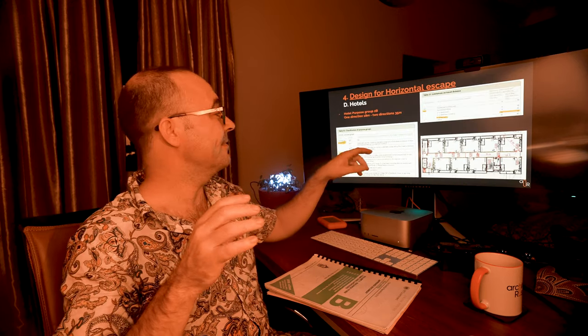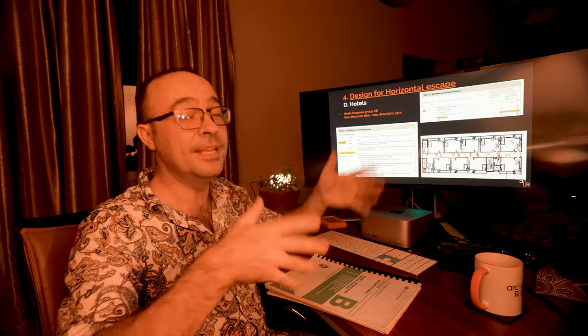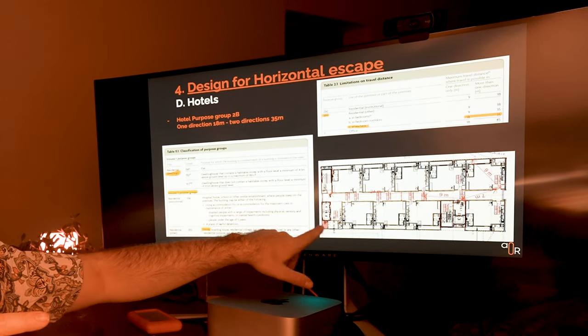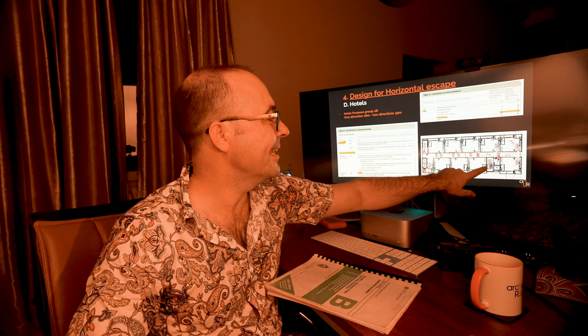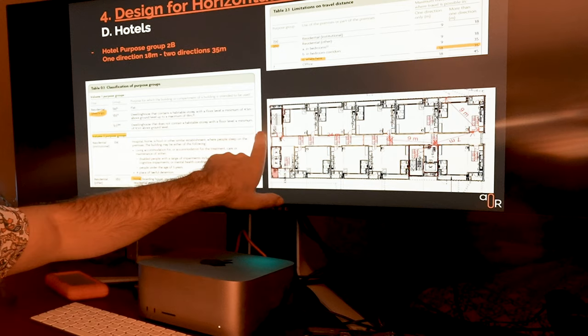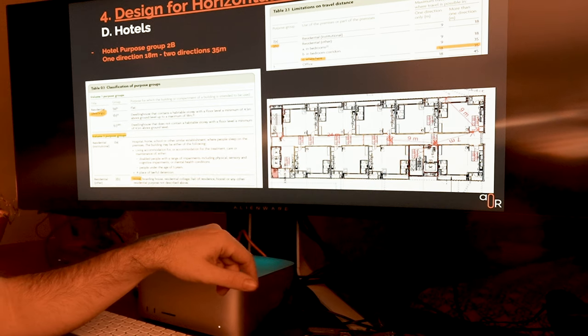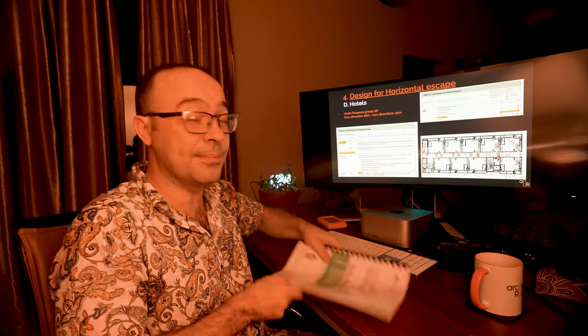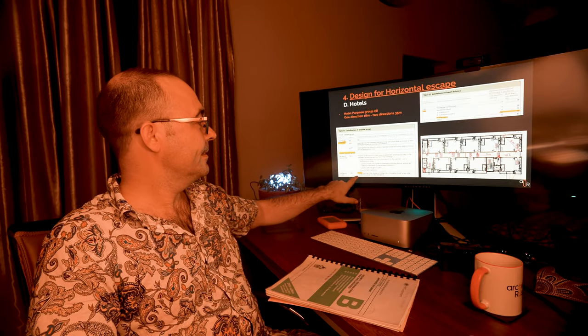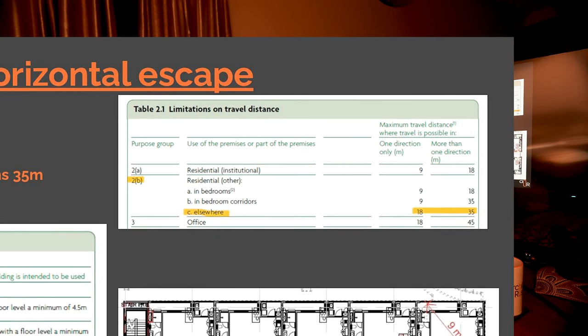For hotels, it's a little bit different. You can go up to 18 meters in one direction from the hotel room door, because these hotel rooms and apartments are fire separated — they'll have a fire door, which we'll talk about later. Then with two directions it's 35 meters. So for a typical long hotel layout, it'll be less than 35 meters with a point of choice. But if you've got one escape at the end, that'll be less than 18 meters. Here's the travel distances table in the document: residential is 18 and 35 meters.